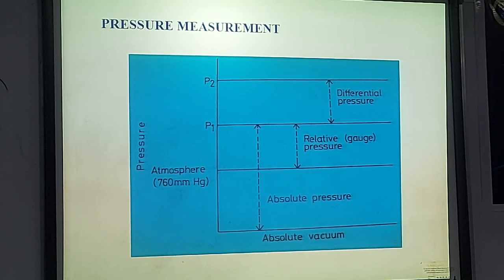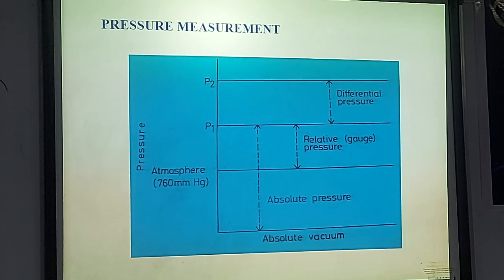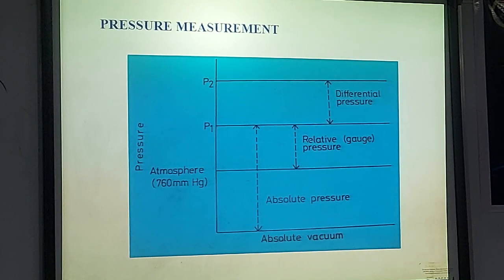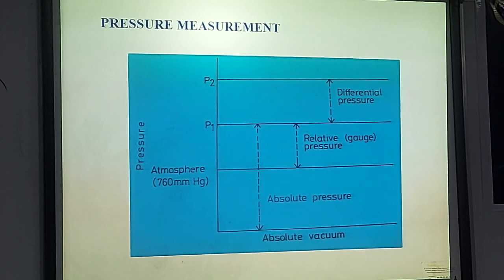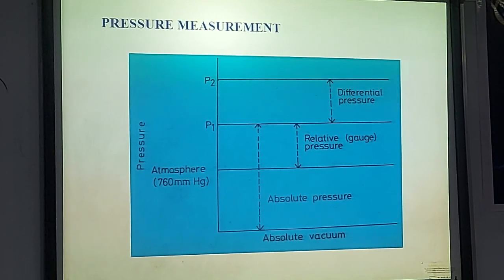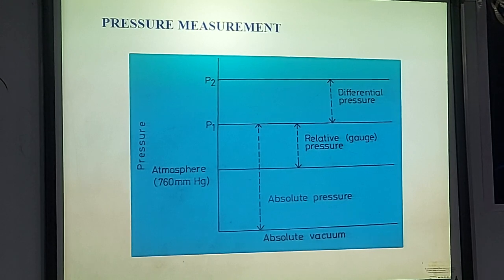or a differential type. Suppose a pressure transducer measures pressure with respect to vacuum—we call it an absolute type pressure transducer. Suppose a pressure transducer measures pressure with respect to local atmosphere—then we call it a relative type pressure transducer. Most biomedical pressure transducers that we see in hospitals are relative type or gauge type pressure transducers.